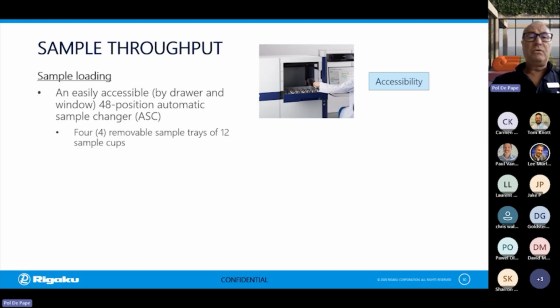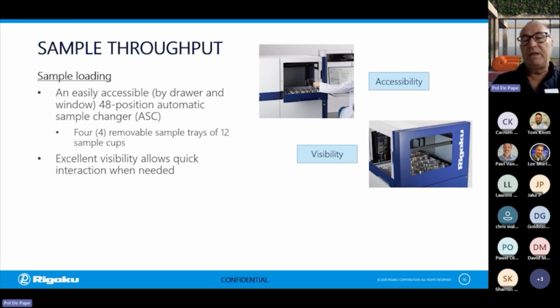Sample throughput is also something we have thought about in great detail. So sample loading is quite easily done. We have a high degree of accessibility into the sample loader. We have a 48 position automatic sample changer. We call this ASC, which you can open by means of a drawer or by means of a door. In that ASC, we can put up to 4 sample trays, which can each contain 12 sample cups, so 48 in total. So you can visualize at any time what is happening inside the sample changer, just to undertake some action if something would go wrong.